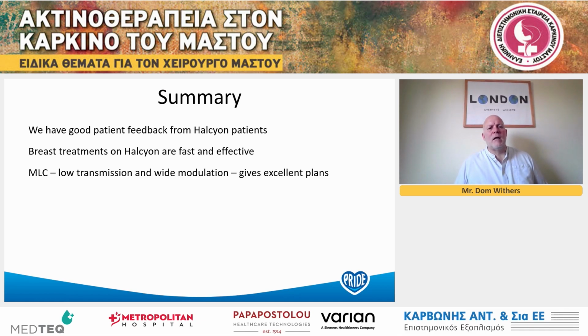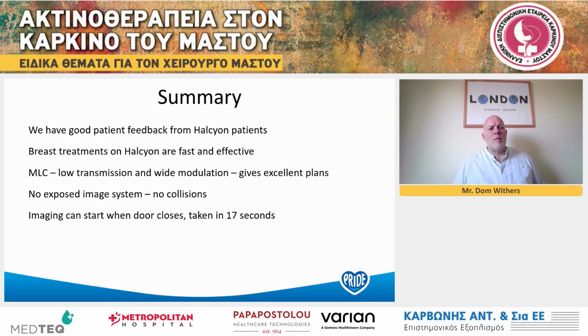With the MLC low transmission and wide modulation gives us excellent plans, and we believe that in many cases we've had better plan quality than we have on our conventional LINACs. And of course, the speed is important for the patient. The speed is important as well for the quality of minimized movement whilst the patient is on the bed. There's no exposed imaging system, so there's no risk of collision, provided you place the patient in the right position in the first place. Imaging can start as soon as the door closes. It can be finished in 17 seconds.